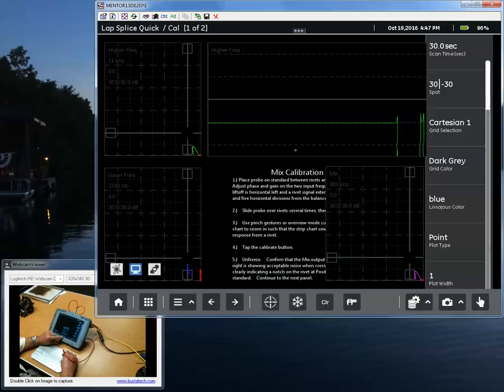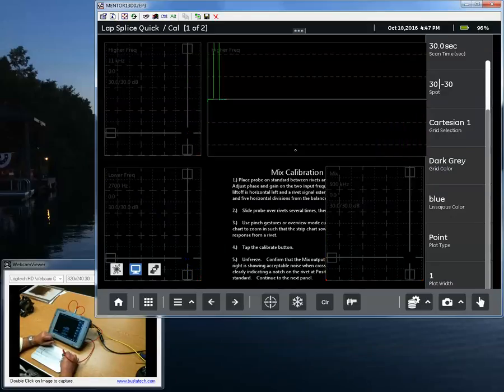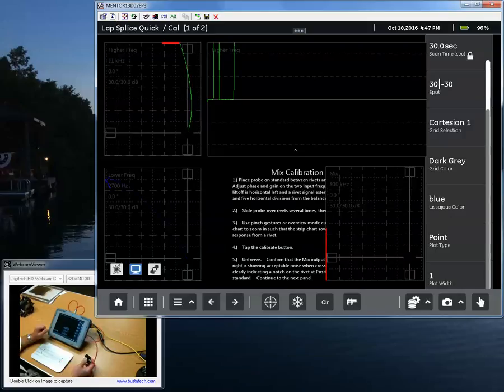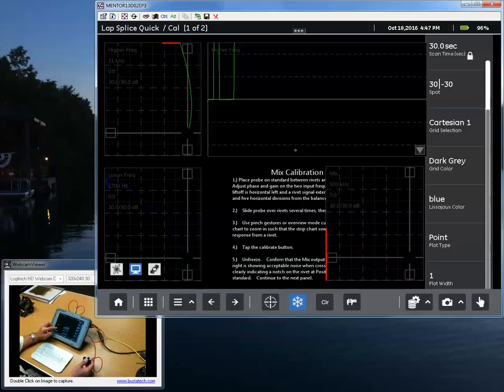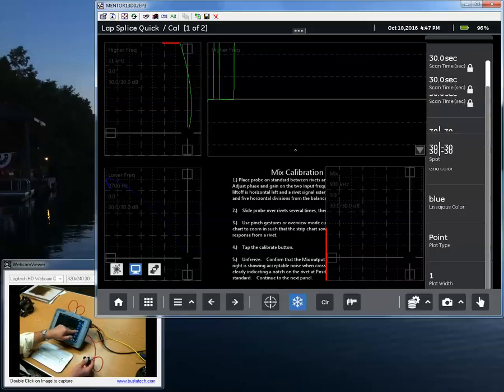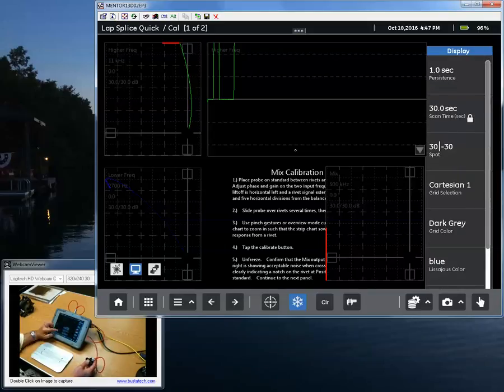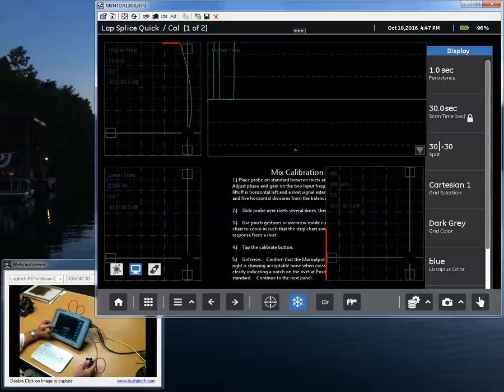As I move my probe, we will balance and show liftoff. You notice my signal is now a series of dots. Each one of those dots is an individual sample. Since our sample rate is set to 600 hertz, if I have one second worth of persistence, I have one second of persistence, so there are 600 total dots displayed on each of the Lissajous at the moment.